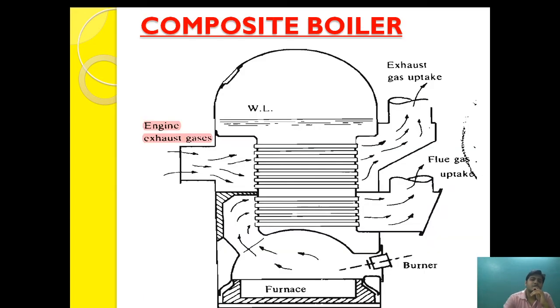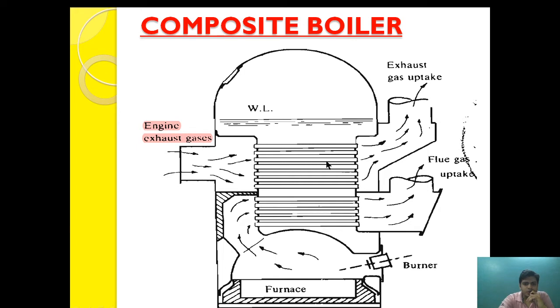First, let's look at the composite boiler. As you can see in this diagram, this is the composite Cochrane-type boiler. The composite boiler generally consists of two parts: one is the oil-fired smoke tube boiler and one is the exhaust gas smoke tube boiler, combined into one boiler. When the engine is running, exhaust gas enters the smoke tube, and the surrounding water gets heated up to produce steam for auxiliary purposes.